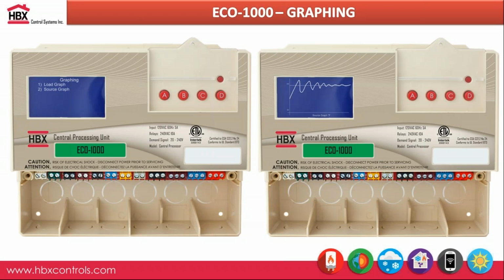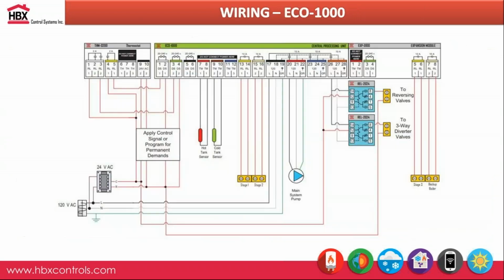The 1000 controller also has the capability of doing some graphing, so we can actually graph the load and the source in terms of heating. This can be used for troubleshooting purposes. Say something has mechanically gone wrong, you can look back up to 7 days in terms of graphing to help you troubleshoot, maybe a power failure, or why you're having some issues on site.